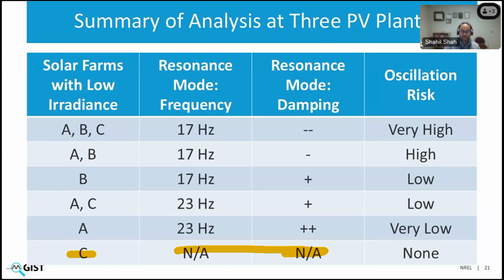When there's plant A only with low irradiance, there is a 23 Hertz mode, but with very high damping. And when plants A and C are within the system, there is a 23 Hertz mode with slightly lower damping, but it is still sufficiently positive. So there won't be any oscillations. And then if only plant B is in the system, which is basically the plant for which I showed you the analysis in the previous couple of slides, the system mode is at 17 Hertz and the damping is positive. So the risk of oscillations is still low.